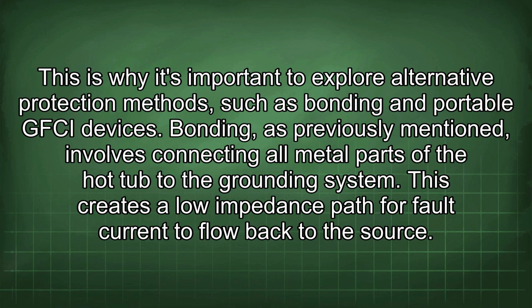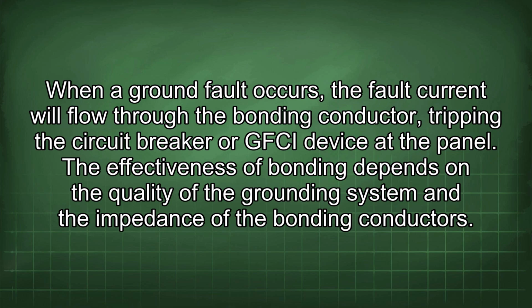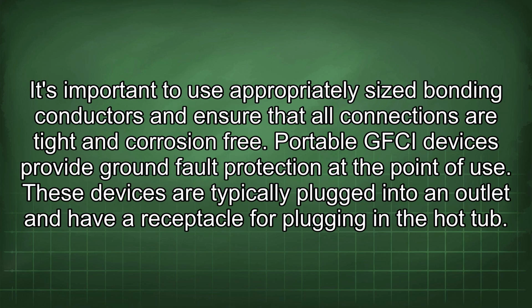Bonding, as previously mentioned, involves connecting all metal parts of the hot tub to the grounding system. This creates a lower impedance path for fault current to flow back to the source. When a ground fault occurs, the fault current will flow through the bonding conductor, tripping the circuit breaker or GFCI device at the panel. The effectiveness of bonding depends on the quality of the grounding system and the impedance of the bonding conductors. It's important to use appropriately sized bonding conductors and ensure that all connections are tight and corrosion-free.